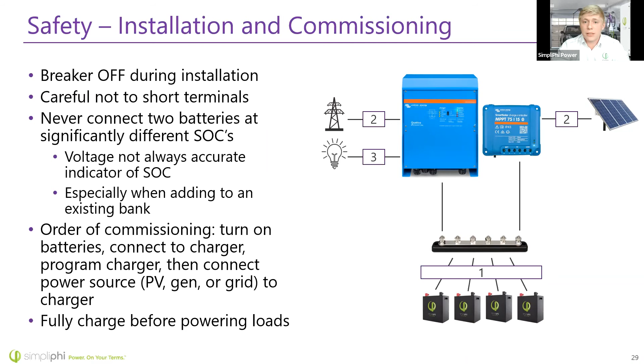So for order of commissioning, once you've got everything installed, you want to first turn on the battery breaker and connect it to the DC bus bar. Next, you're going to connect the charge controller to the charging source and let the batteries charge up fully before turning on the inverter and loads. Alternatively, if you do not have a charge controller and you're charging the batteries from the grid, you will have a loads breaker and an input breaker. So you'll want to have the batteries on, that'll turn the inverter on, and then you can initiate a charge by connecting the AC in, but do not turn on the loads breaker until the batteries are fully charged. This is because the batteries do not ship fully charged. They're not allowed to. They ship at about 20 to 30% state of charge due to regulations around transportation.